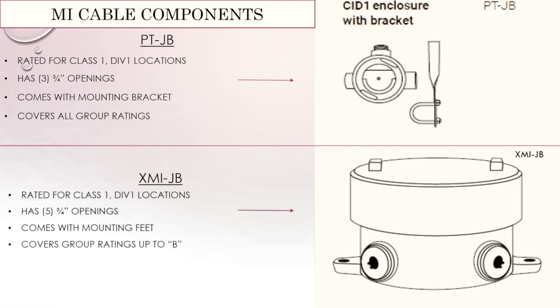The XMI JB is also Class 1 Div 1. It's a little smaller than the PT JB and has five different openings to choose from. It comes with mounting feet, so it doesn't require a separate bracket. However, it does not cover Group A in Class 1 Div 1 — it covers the remaining groups. Those are the MI cable components we handle.